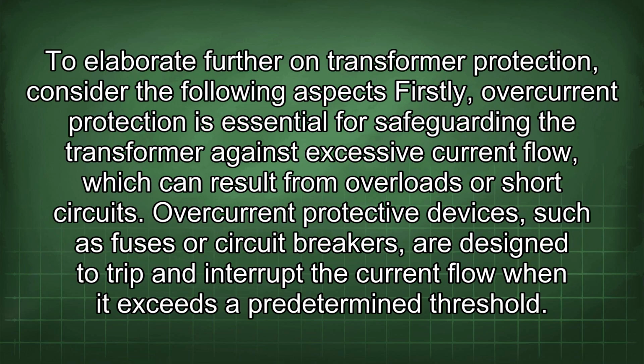To elaborate further on transformer protection, consider the following aspects. Firstly, overcurrent protection is essential for safeguarding the transformer against excessive current flow, which can result from overloads or short circuits. Overcurrent protective devices, such as fuses or circuit breakers, are designed to trip and interrupt the current flow when it exceeds a predetermined threshold.